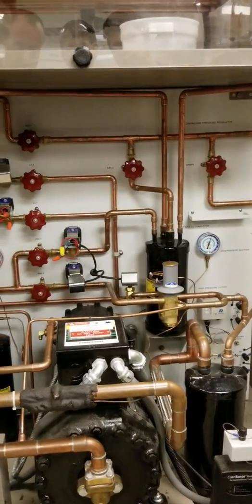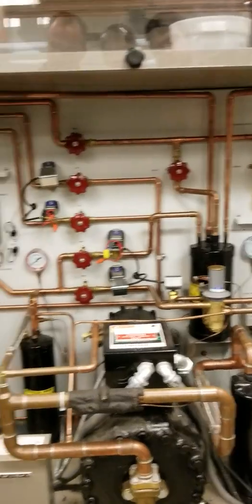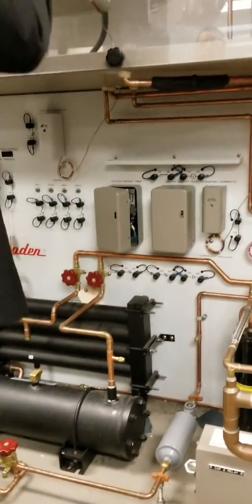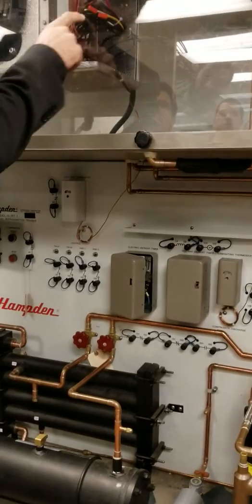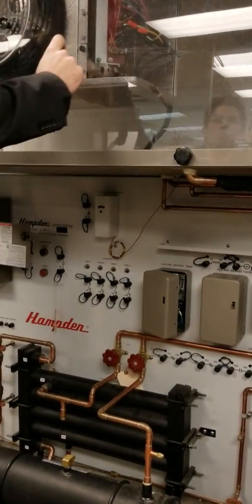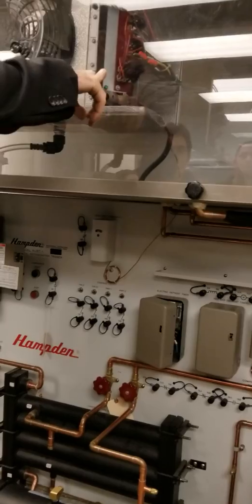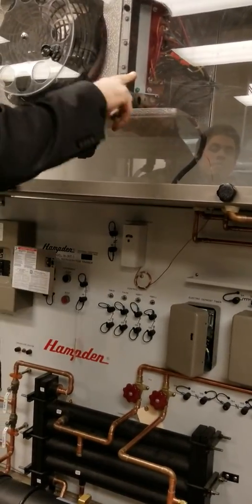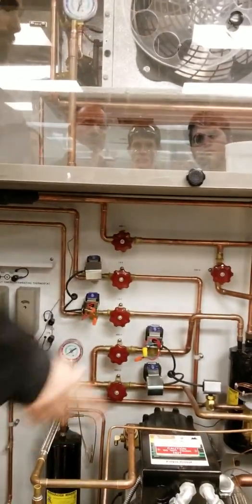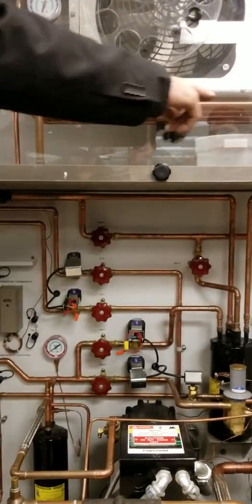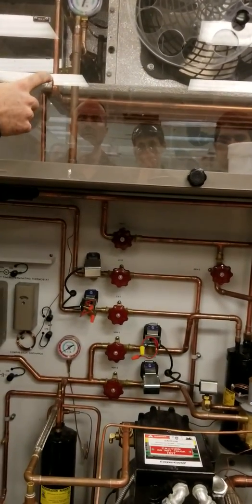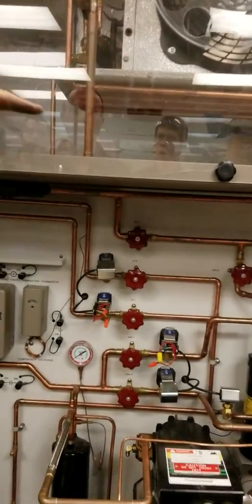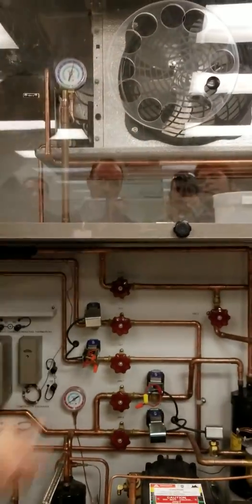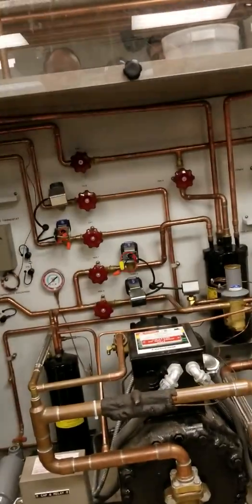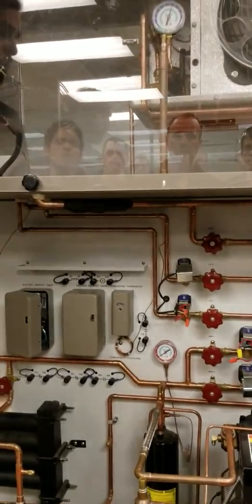where if we need to defrost, there's two different methods of defrost it uses here. We have an electric defrost, which is basically a filament wire that runs along the bottom of the drain pan, which will be energized probably with like 120. It's going to get hot, it's going to make that water evaporate. We have another style, which is with our hot gas. It'll directly drop our hot gas into this bottom rack. If you look at the bottom of this unit, you can see the rack and the arrangement of how it is. And that's going to help warm up that pan and also just evaporate the water.